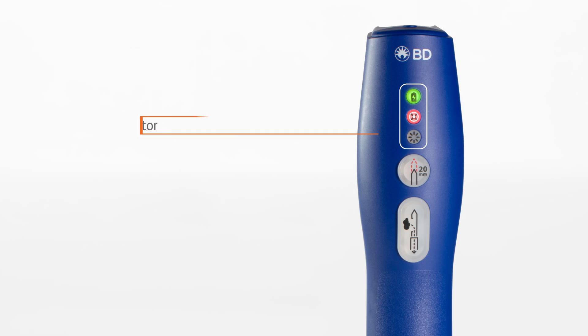Key features of the driver include 3 indicators. The error indicator visually and audibly alerts the user that action is required in order for the unit to become operable. The battery indicator shows the driver's charge level. The smart mode engages when the driver needs extra time to sample. The prime pierce button initiates the optional prime pierce sequence. Finally, the sample button is engaged to collect tissue samples from the breast or axilla.